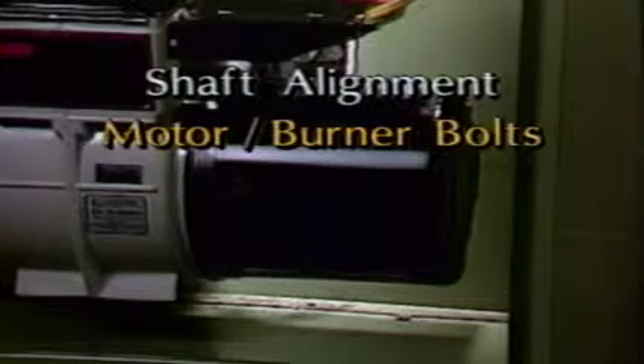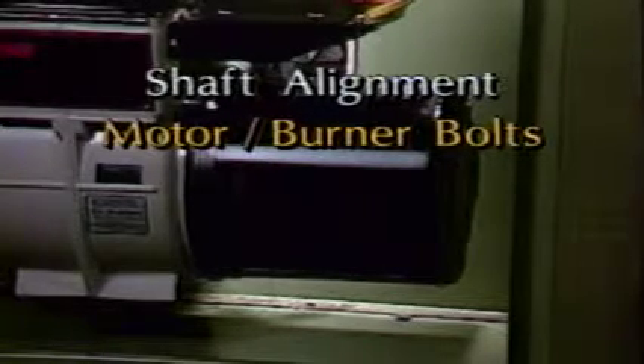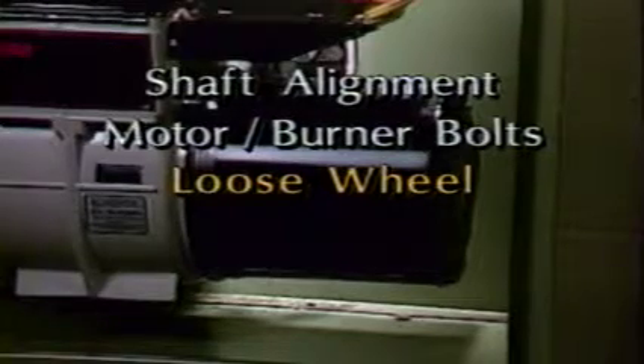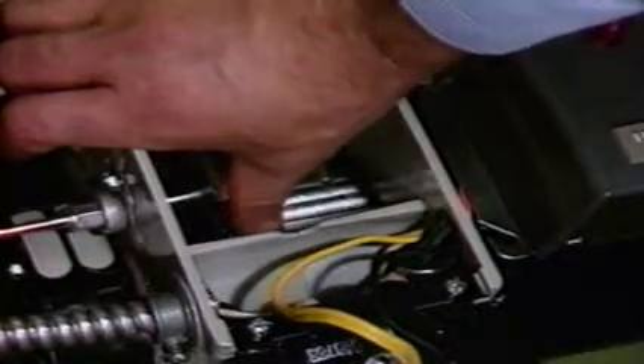Noisy motor operation. Check the shaft alignment with the coupling. Tighten or loosen the motor-to-burner housing bolts in an alternate manner. Check for a loose blower wheel. Check for excessive radial shaft play. Check for loose start switch parts. Bound pump shaft. Check the coupling for slippage due to stripped end caps. Also check to see the coupling has not sheared away from the end caps.